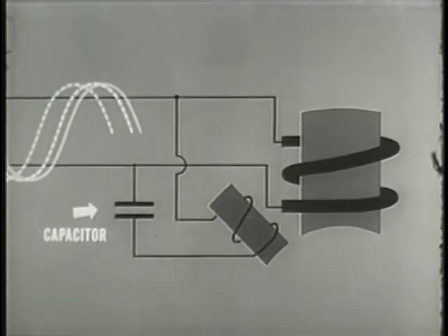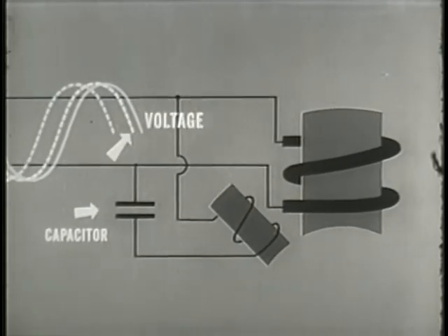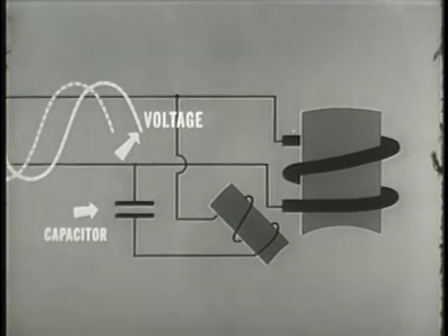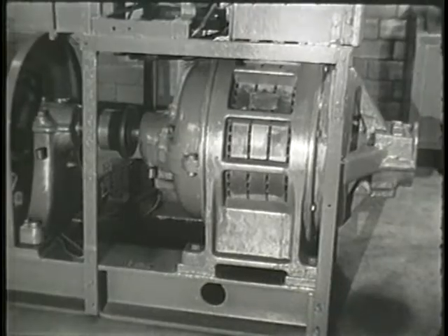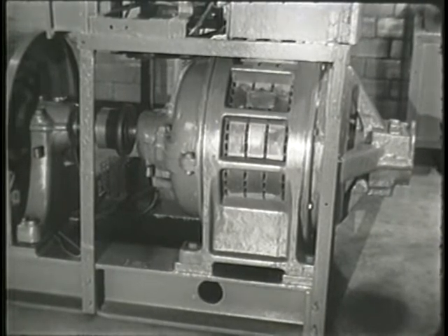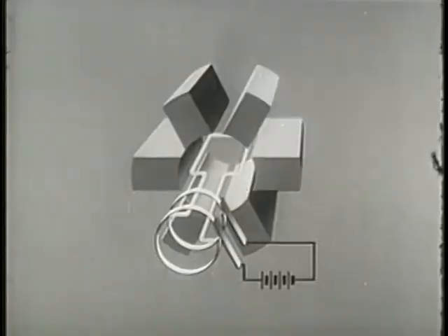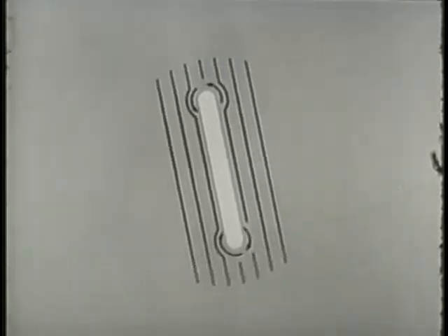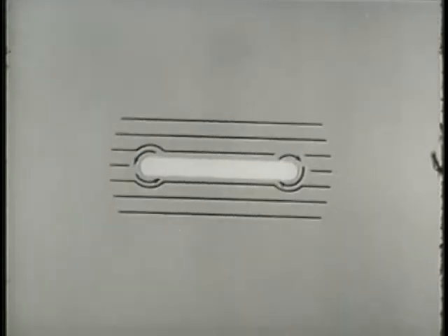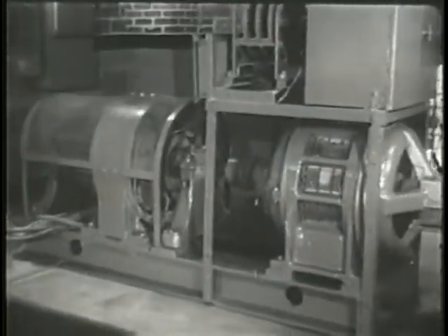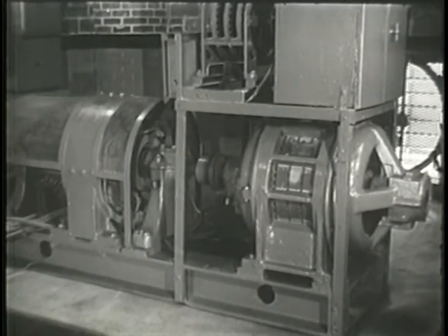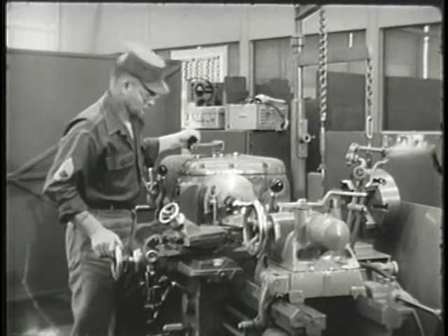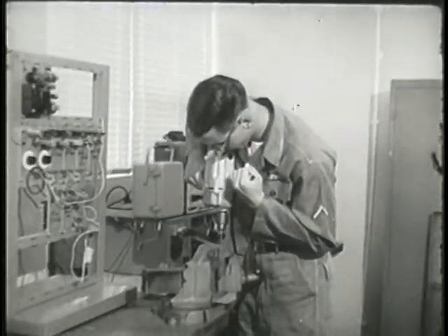In the third method, a capacitor is placed in series with a starter winding. This causes a greater phase shift between the two windings. We now have two-phase operation on single-phase voltage. In synchronous motors, there is no need for relative motion. The EMF needed for the rotor is supplied from an outside DC source. Here, the rotor and the revolving field rotate at the same speed. AC rotating electrical equipment is the most practical for a multitude of uses. Knowledge of the principles of alternating current is essential to intelligent operation of such equipment.